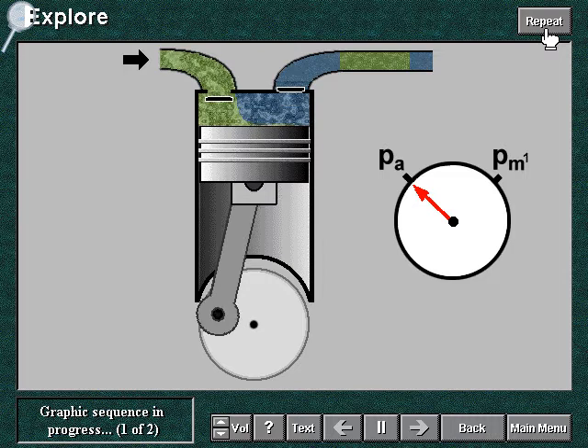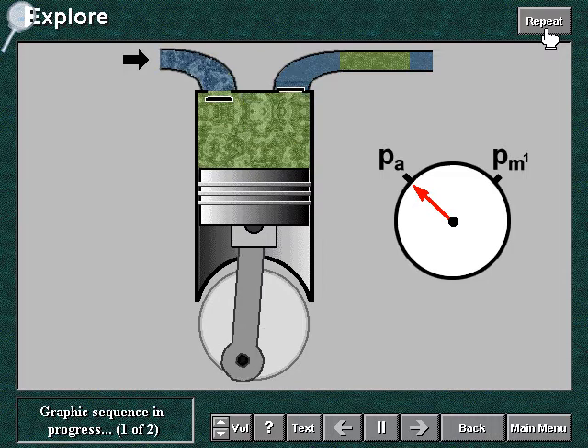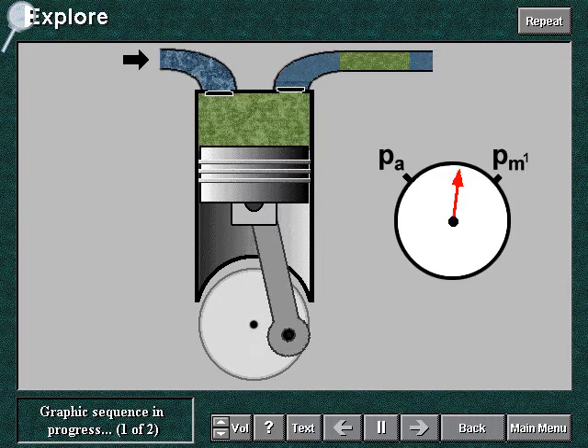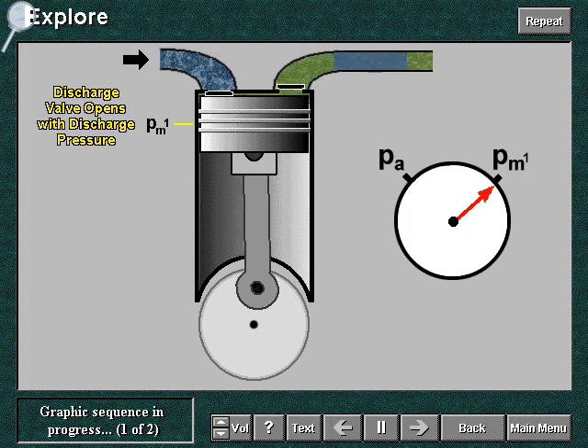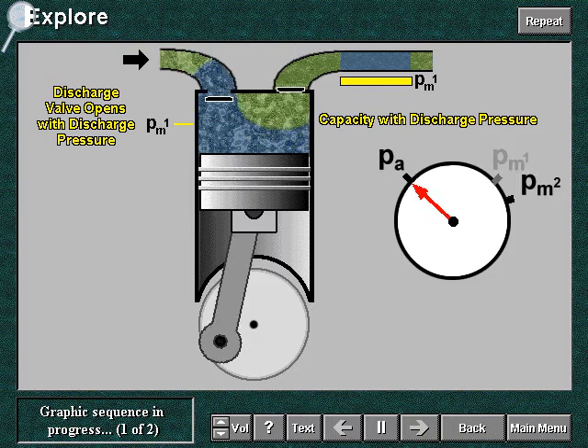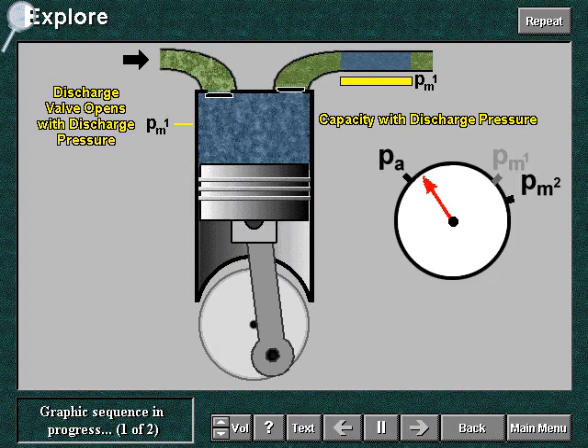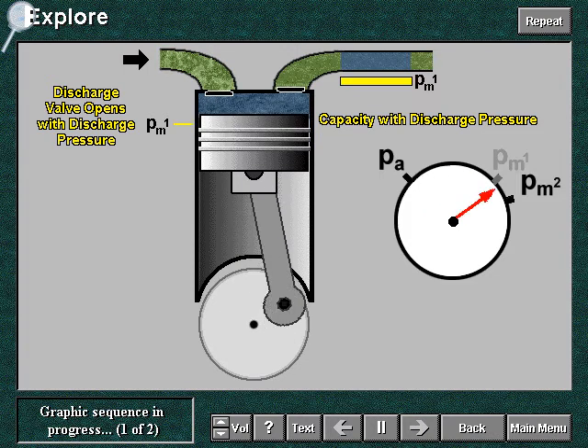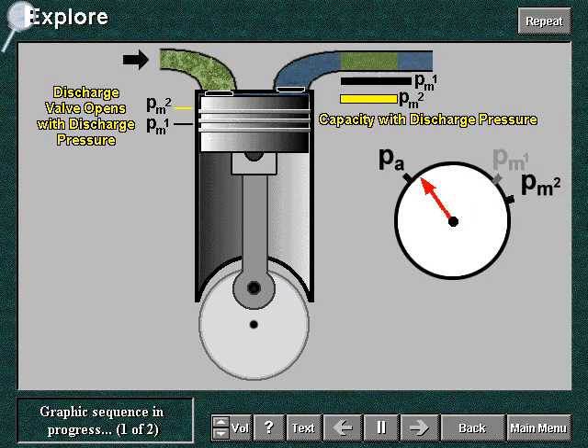Consider now a single stage compressor. If a higher delivery pressure happens, the compression ratio is increased and volumetric efficiency decreases. Less gas is delivered to the user and the compressor capacity is decreased.